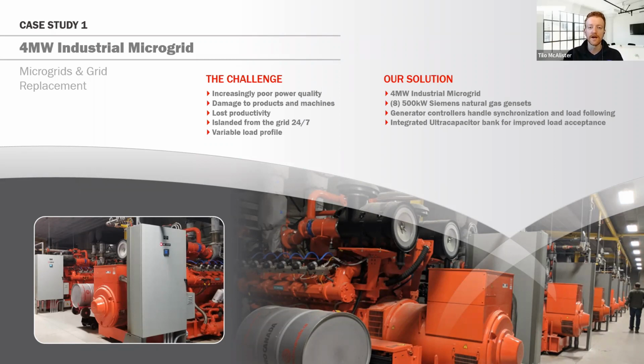One of the design considerations in this project that the customer had requested, one of the reasons we used 8 smaller units in addition to the load acceptance capabilities that they offered, is so that if the project changes and needs to be reevaluated in the future, these engines can quite easily be remarketed elsewhere and sold on the used market, because they're a 500 kilowatt continuous rated natural gas engine that's in very high demand.